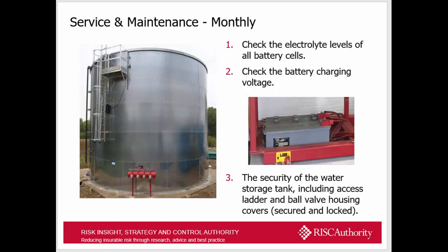Moving on to monthly tasks, there is a requirement to check the electrolyte levels of all battery cells and check the batteries are charging. Also, check the security of water storage tanks, including access ladders and valve housing, to ensure they are secured and locked. The reasons why tank security is so important will be covered later in the presentation.